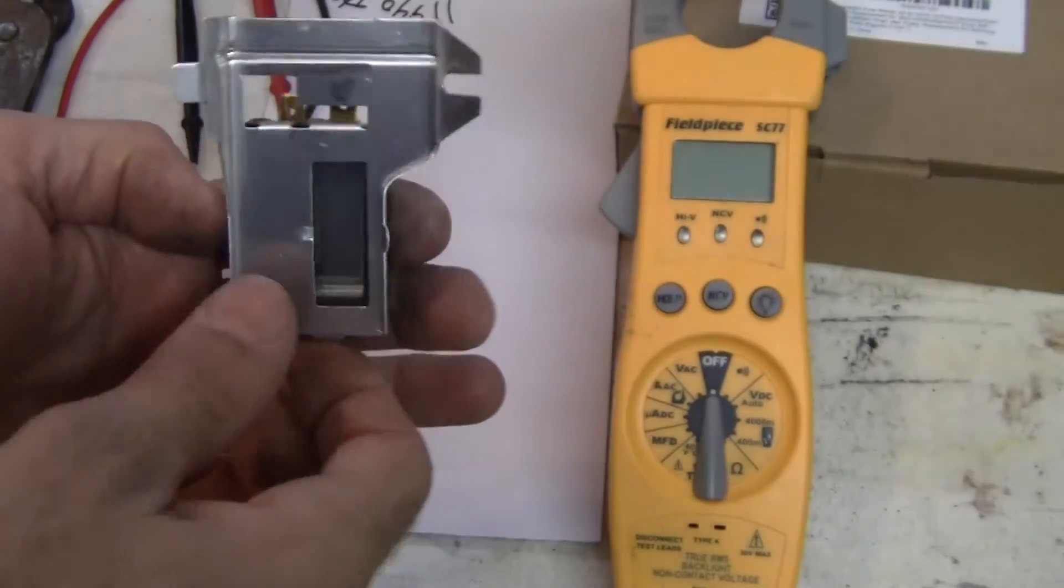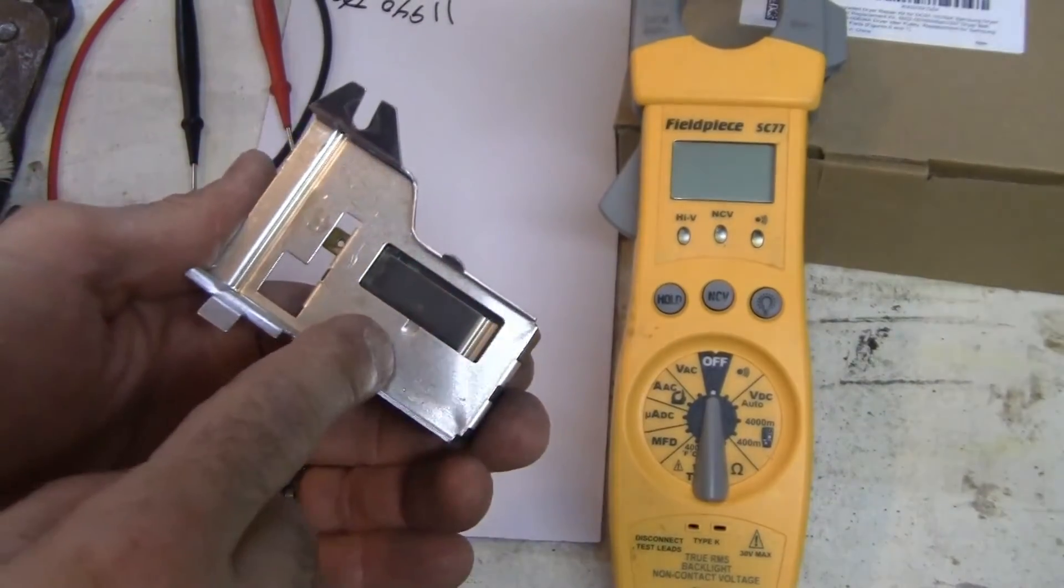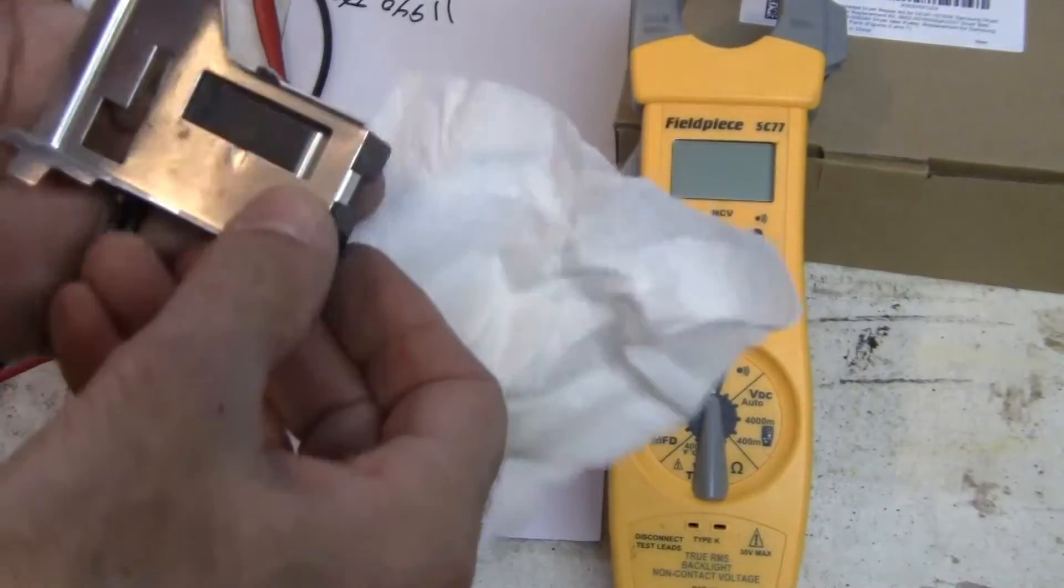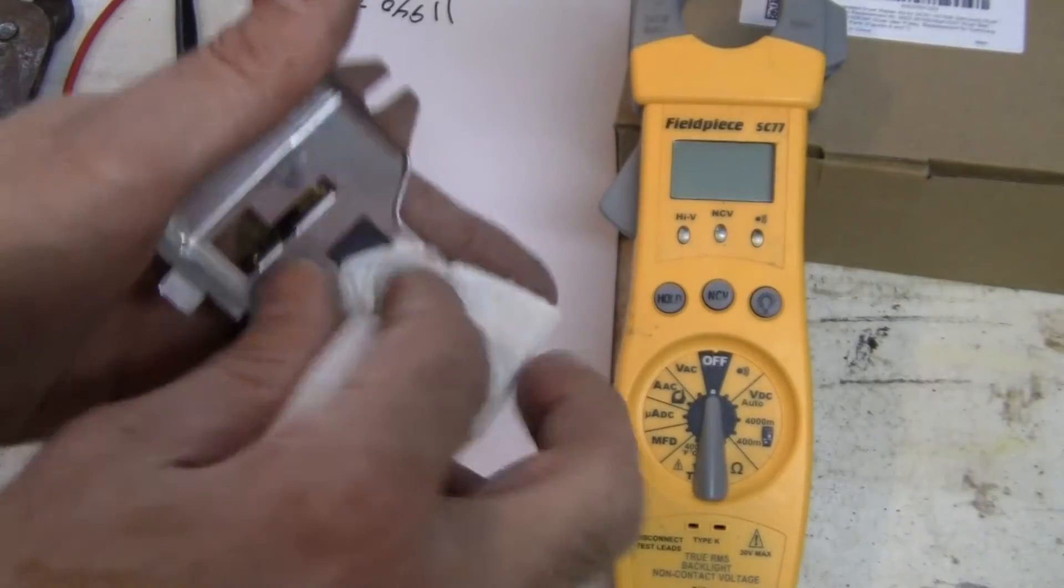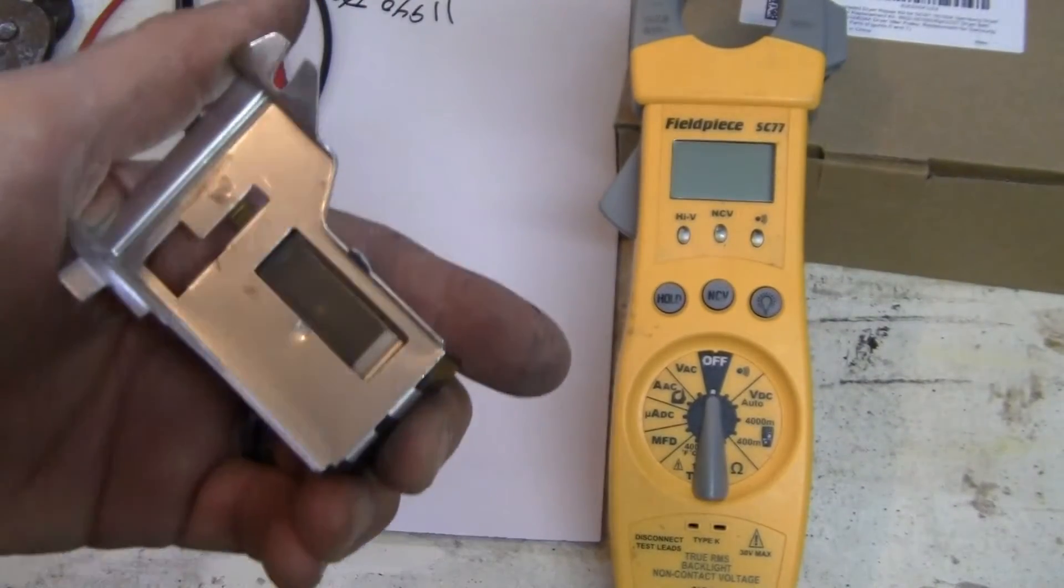All right, so there's not much to this. There's a little window right there. We can make sure that the window is clean, just to make sure that there's no obstruction from it seeing the flame.